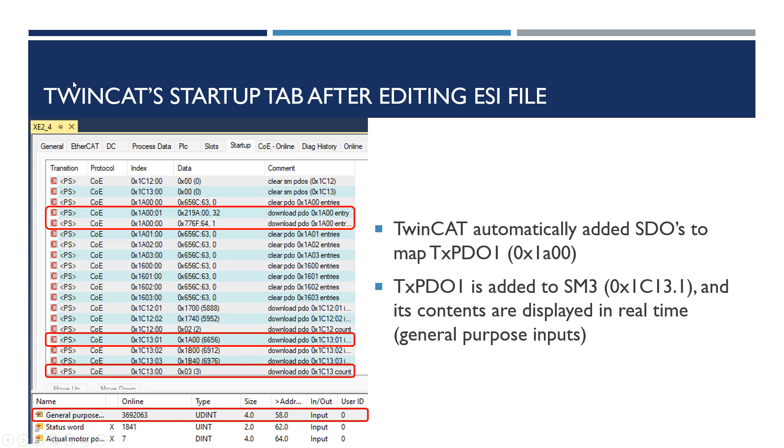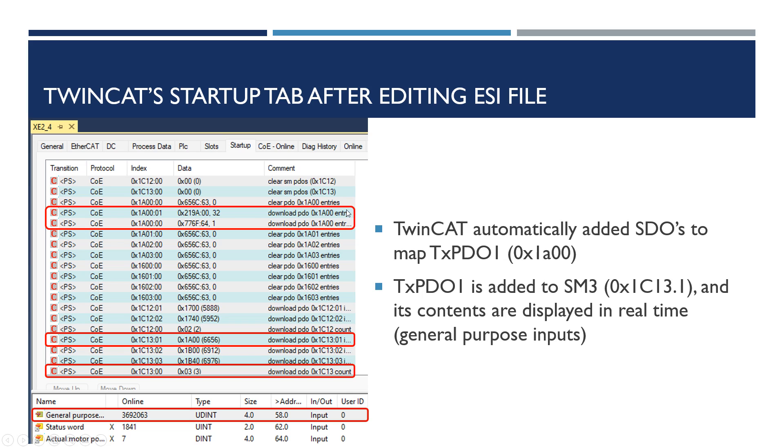Here's TwinCAT's startup after editing the ESI file. I edited the ESI file to edit that PDO, and TwinCAT automatically saw that and automatically added these SDOs to the startup sequence. I didn't have to add these, it added them for me from reading the ESI file. Now we can see that this is three, the SM3, meaning that now we have three objects instead of just two mapped inside of the TPDOs.